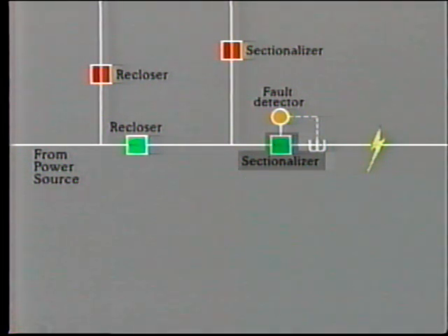In order to do this, the sectionalizer control circuit must count the number of times that the recloser has tripped and reclosed, and it must also register the fact that fault current is passing through the sectionalizer. We certainly do not want other sectionalizers tripping unfaulted circuits. When the sectionalizer detects a heavy flow-through current, it starts the counter. This is often referred to as resetting the counter. The counter registers the number of times that voltage falls to zero as a result of the recloser tripping.